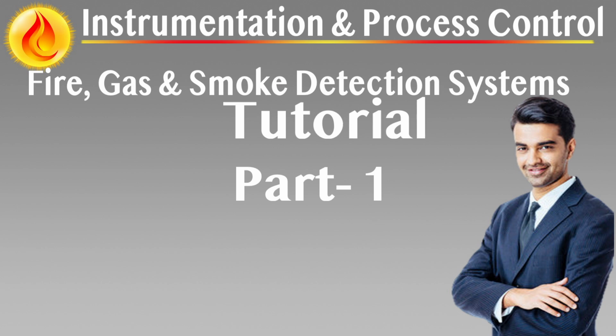Environmental and operational considerations. Point gas detectors should not be installed lower than 1 meter above grade unless specifically required to avoid water ingress or mechanical damage. When installed in difficult-to-access locations, permanent calibration fixtures should be added for single-person testing and maintenance. Key considerations. Placement near potential leak points, e.g., compressor seals, flange connections, valves.